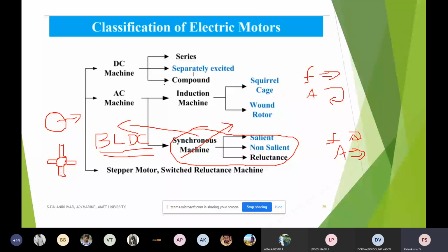Electrically, the rotor always needs to be contacted. That can be overcome by simply reversing the arrangement: the field is rotating and the armature is stationary. The field excitation that is required may be produced by an induced EMF with a rectifier arrangement, which is one bundle coupled and fixed on the rotor side. Whenever the stator is given supply, there will be an induced EMF. That EMF will be converted to DC, providing the excitation.